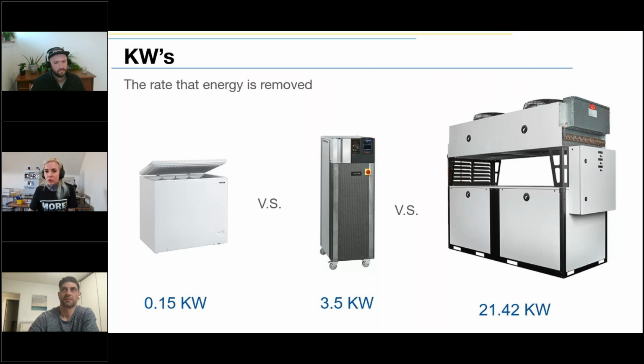The size of the reservoir on those little heaters explains why they're 2 kilowatts, because they're designed for systems heating maybe 1 or 2 liters of fluid. So if the reservoir on your heater or chiller doesn't at least match the jacket volume of the vessels you're trying to heat or chill, you're not going to get very far, because you'll run out of that built-up, stored energy.